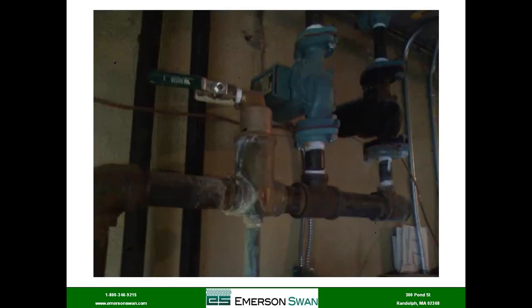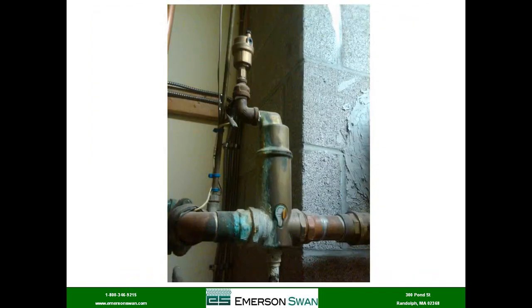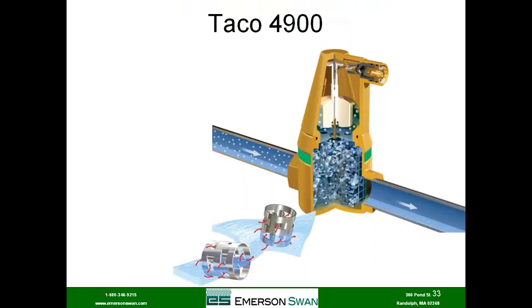One of the things on spiral vent is that they leak a lot, and guys have sent me pictures from the field of very creative ways to stop the leak. Here's one. A guy installed a ball valve in the barrel. There's another guy that got very creative with several fittings and a high vent just to get rid of the air. I'd say they've done a few things, but they all leak because there's no shutoff valve. There never was. There's no shutoff valve in the barrel.